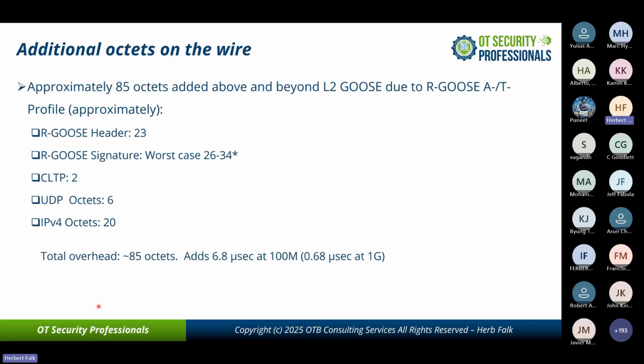If you compare layer 2 GOOSE to R-GOOSE, as an estimate, there are about 85 octets added to the packet. If you're at 100 megabits, that adds 6.8 microseconds of transmission latency. Still well within 3 milliseconds, so it's not a real issue.